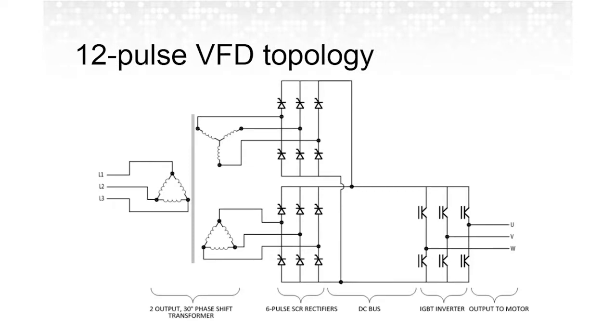Moving on to the next slide, this is the next step up from a 6-pulse VFD, a 12-pulse VFD. If you squint your eyes, you can see at the bottom something that sort of looks like a 6-pulse drive. A 12-pulse VFD is essentially 2 6-pulse VFDs grafted together. They have a common output, but you can see that there are 2 rectifier input sections connected to a 30-degree phase shift transformer. Each of the outputs of the transformer feeds one of the rectifiers, which in turn are connected to the common DC bus. Because of the phase shift, instead of taking power at the top and bottom of the input sine wave, we can draw power 12 times for each complete sine wave.